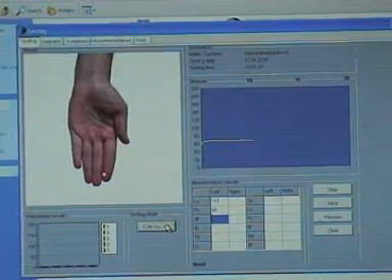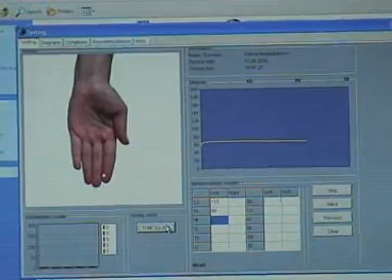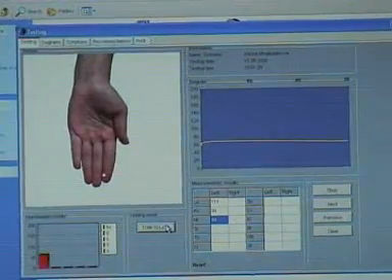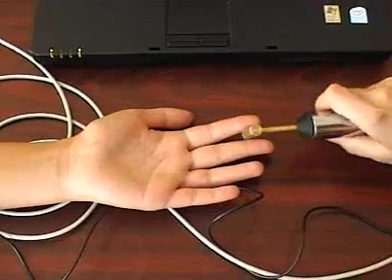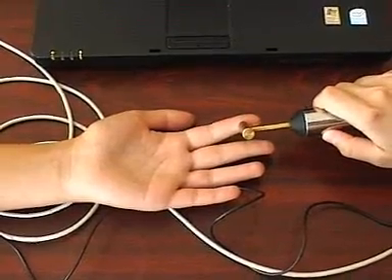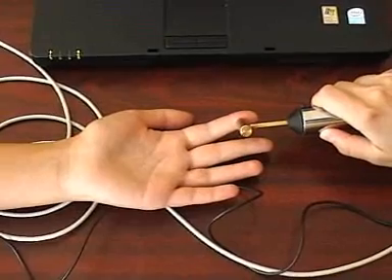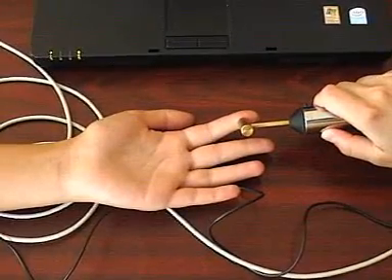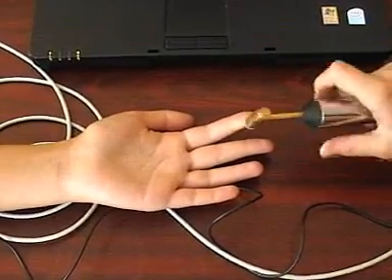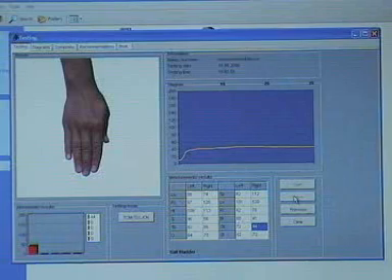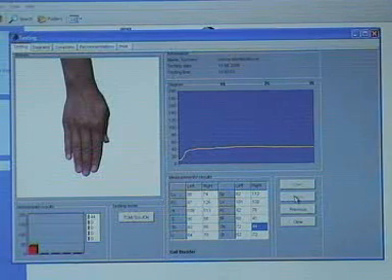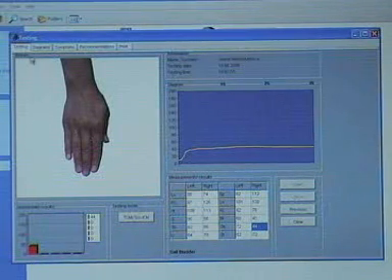After 3 seconds when the yellow line has stabilized and reached the end of the display scale, you need to press the small black push button on the probe. On completion of measurement at the last point, press the Save button in the software.